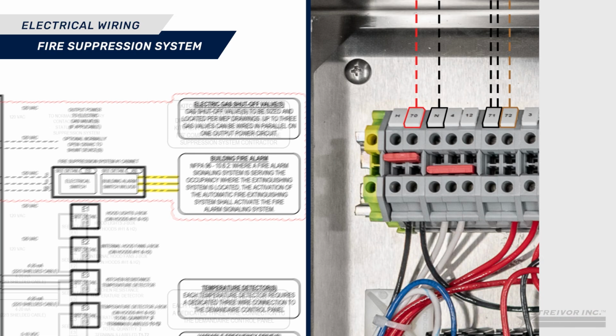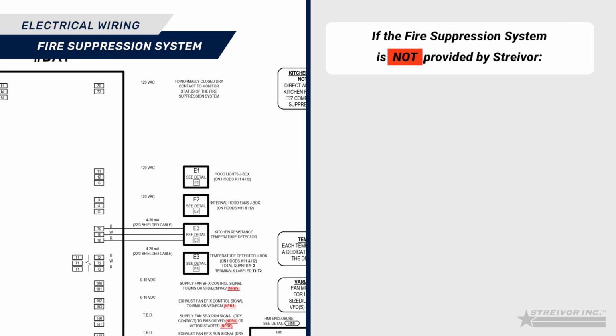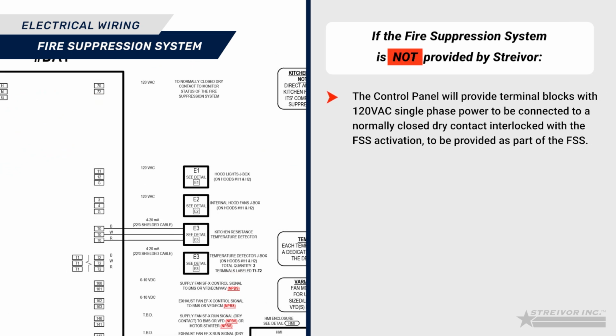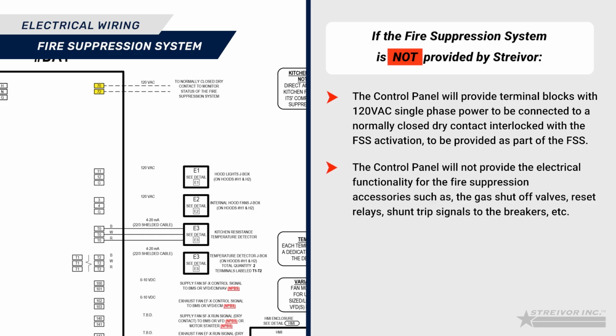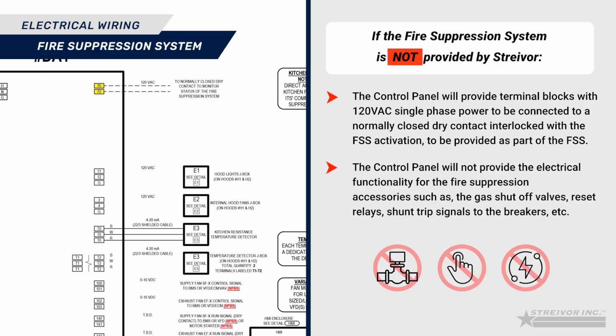If the fire suppression system is not provided by Streivor, the control panel will provide terminal blocks with 120 VAC single-phase power to be connected to a normally closed dry contact interlocked with the FSS activation to be provided as part of the FSS. The control panel will not provide the electrical functionality for the fire suppression accessories, such as the gas shut-off valves, reset relays, shunt trip signals to the breakers, etc.